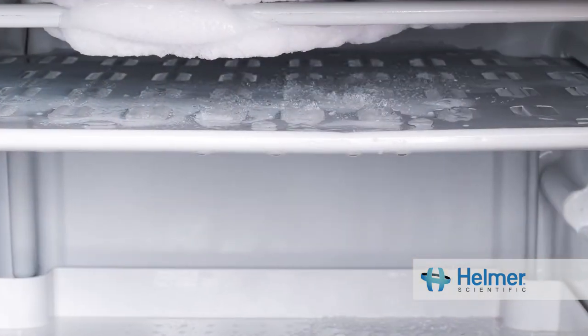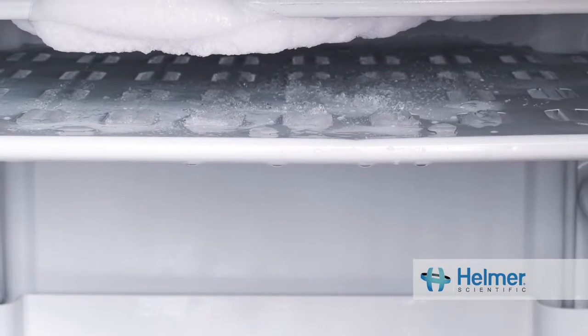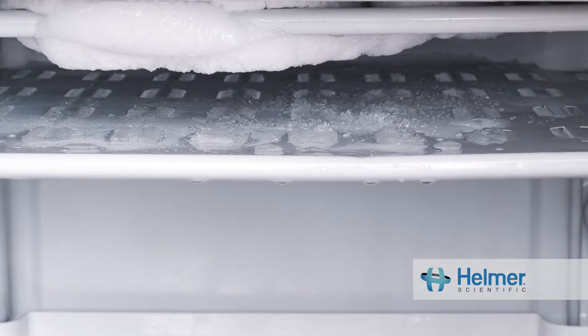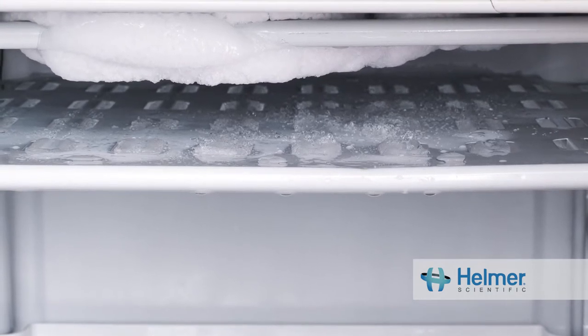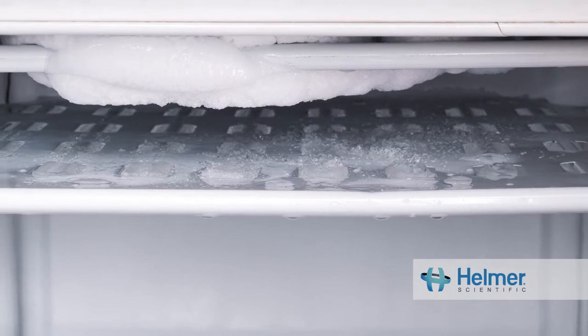Because of household refrigerator design, the refrigerator portion is prone to freezing, and the freezer portion will often have trouble maintaining cold enough temperatures. In addition, these units typically have hot and cold spots, making some locations unsafe for the storage of vaccines.